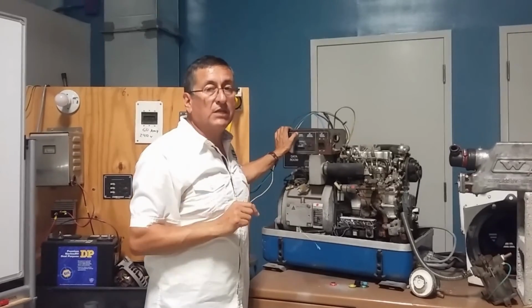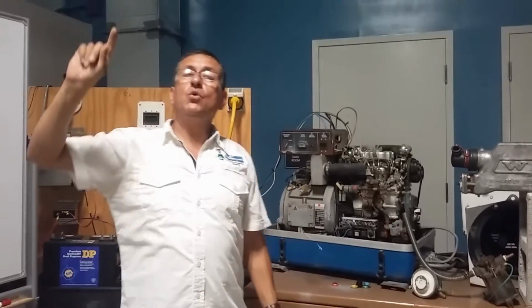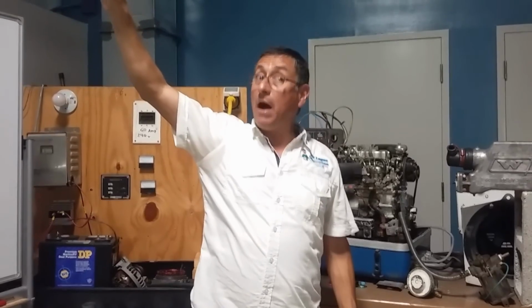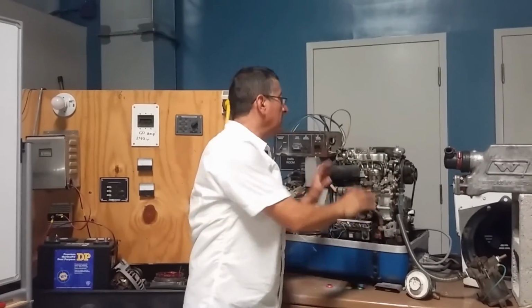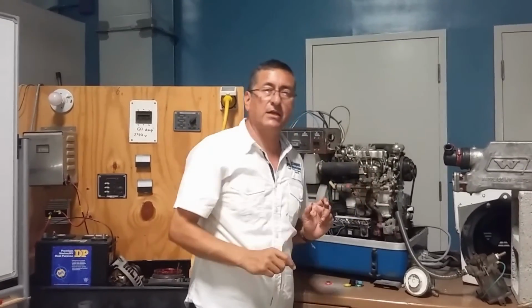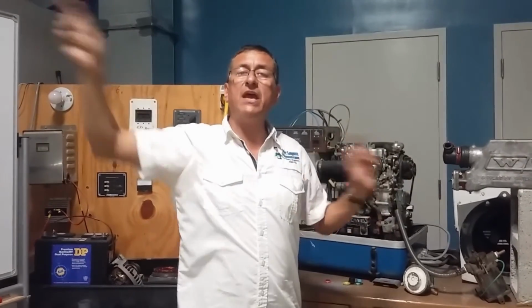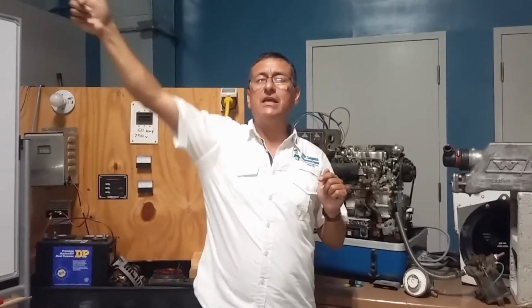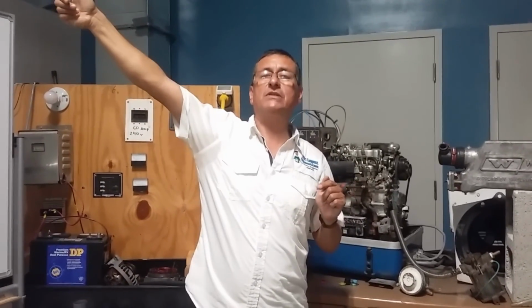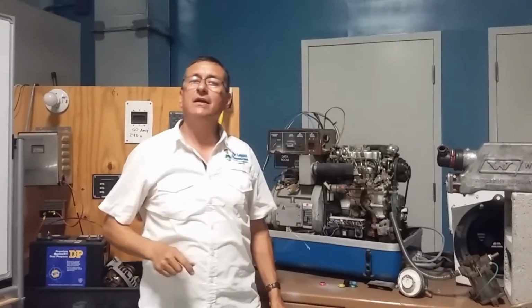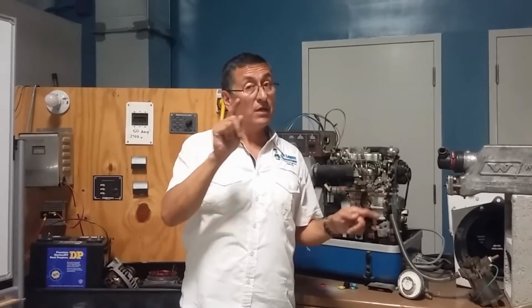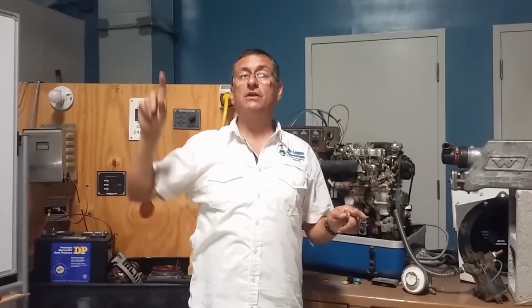Another important thing: remember, if you feed the remote panel, the positive DC for the remote panel is coming from another group of batteries different from the group of batteries for the engine, for the generator. Both groups of batteries should be connected together at the negatives. If not, the signal from the panel to start the generator never passes if the negatives are not connected together. You remember that recommendation in chapters 3, 4, and 5 of the electrical book?